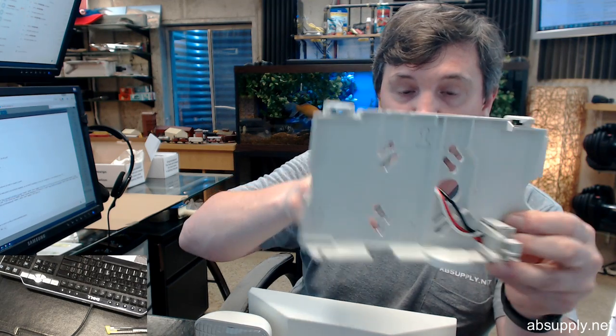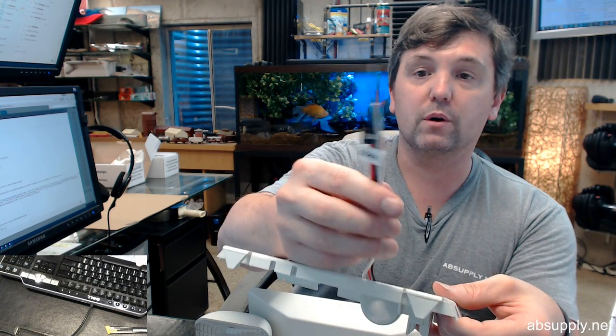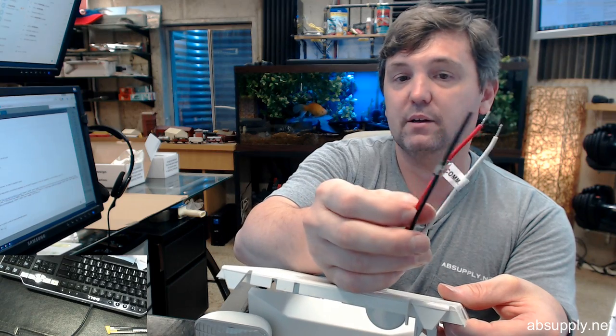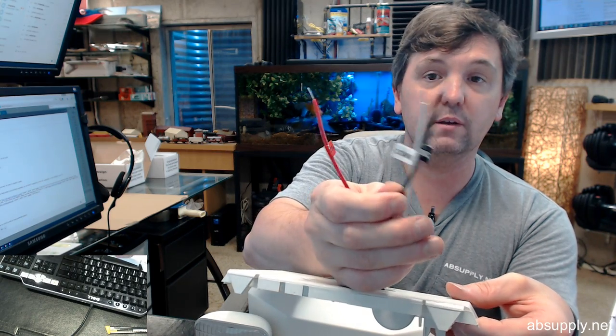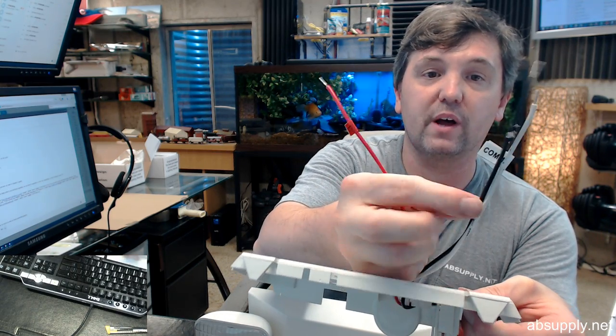Okay, getting that mounted. You've got your common, then you've got your black, and then you've got your red, 120, and then 277 obviously for the red, and then of course the white common. And that really is everything on page 1 of the installation instructions. Page 2, which I actually have open in front of me. Connect the battery to the circuit board using the jumper, which is figure B. Figure B, of course, is going to be on the bottom of page 1.